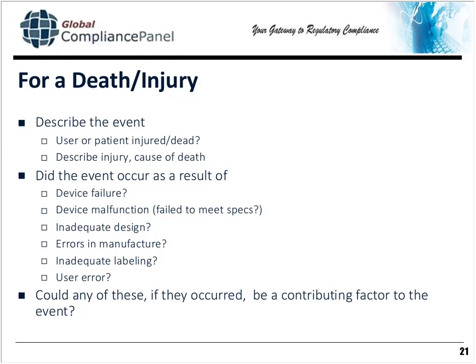Okay, for a death or injury, you should be describing the event. And did the event occur, in your opinion, as a result of any of these things? A failure of the device to operate, a malfunction, inadequate design, an error in the manufacture, that is, this particular lot of device you've discovered had a mistake in manufacture, inadequate labeling, that is, your instructions are not as clear as you thought they were when you first released the device, or was it a user error? And with user error, you don't just relax and say, well, that person didn't know how to use the device.